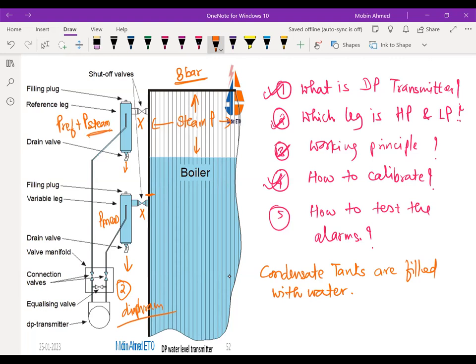So never do anything from here, the drain valve, and if you are going to, you have to be very cautious, because there is a steam pressure on both the sides, this side also and this side. If you open the drain, this side is very high pressure, P reference plus steam pressure. And here your steam pressure is out. Only P measure will be there. So it can damage the DP transmitter. So basically, how to calibrate this one? The calibration is done basically, okay.